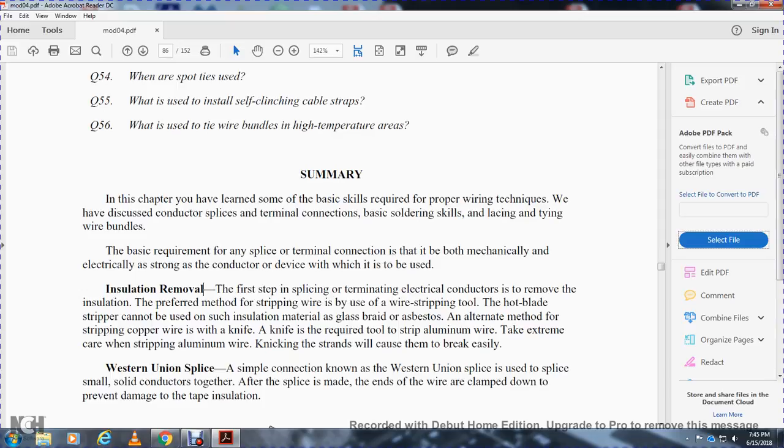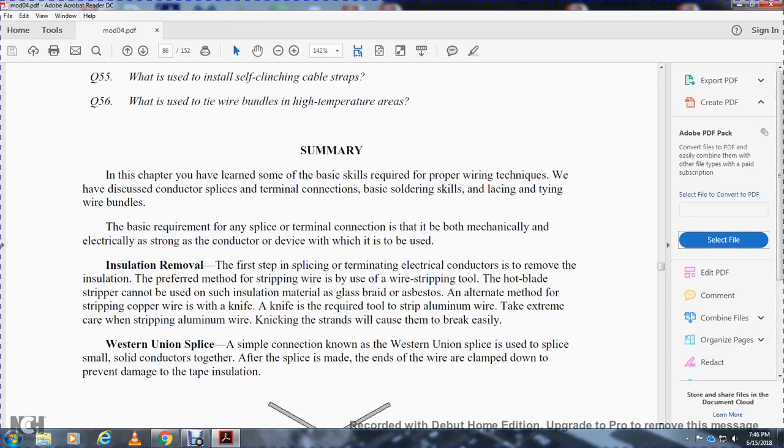Insulation removal. The first step in splicing or terminating electrical conductors is to remove insulation. Preferred stripping methods include wire strippers, stripping tools, or hot blade. The hot-blade stripper cannot be used on insulation materials such as glass braid or asbestos. Alternative methods include stripping copper wire with a knife. A knife is required as a tool to strip aluminum wire, taking extreme care when stripping aluminum wire, as nicking the strands will cause damage and the wire to break easily.